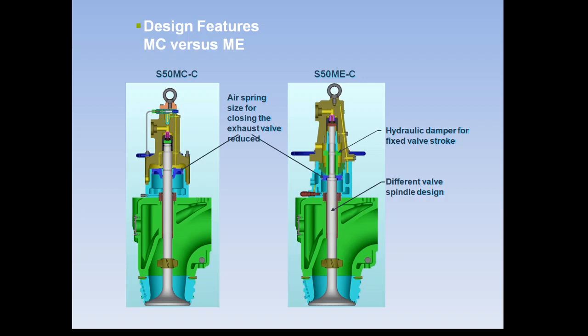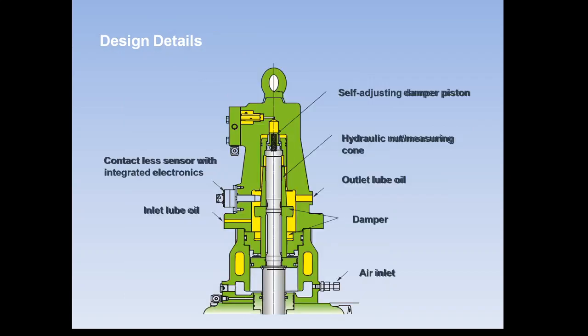So these are the basic differences between the MC series and ME series exhaust valve. First, a feedback sensor has been provided. Second, sealing oil is supplied from the tapping of the hydraulic piston cone for lubrication. Third, a hydraulic damper has been provided for better smooth opening and closing. Fourth, the air spring size has been reduced. And fifth, the spindle design has been changed for accommodation of the hydraulic cone.